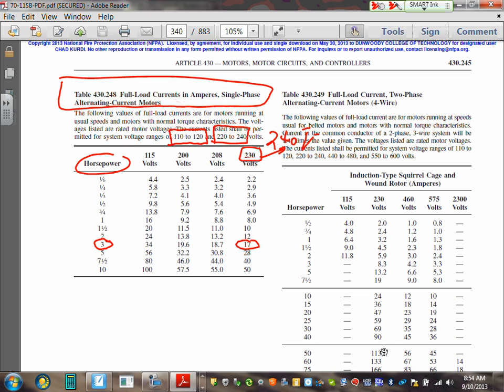2.2. If the voltage of this was 120, where would the 120 go? Between 110 to 120, you're going to go right here, 115, right? Closer. So if it was a 3 horsepower, 120 volt, the full load current would be what? 34. This is called full load current from the NEC. Can I have thumbs up, Chad? We know how to do that. Good. So let's take a snapshot of that baby.